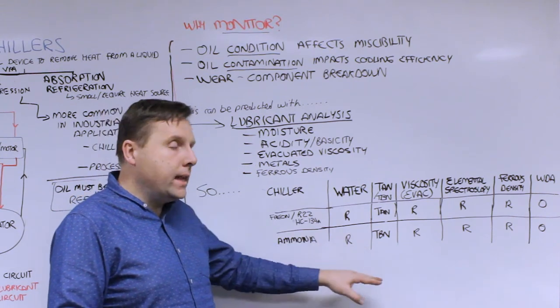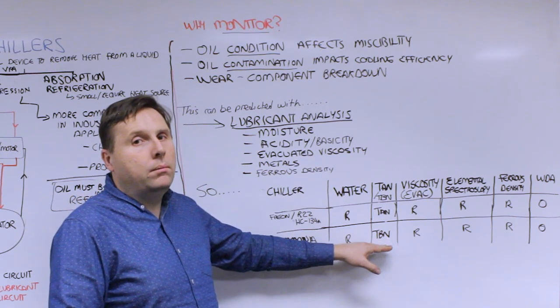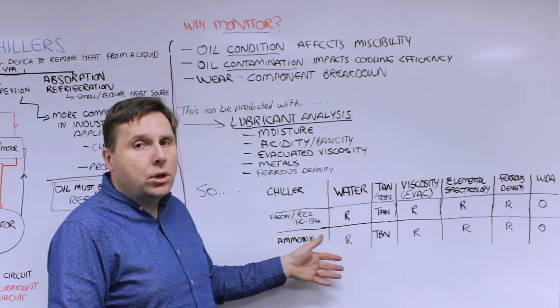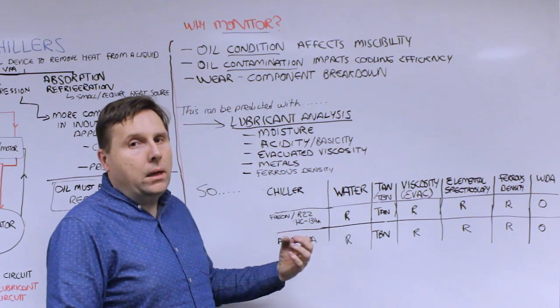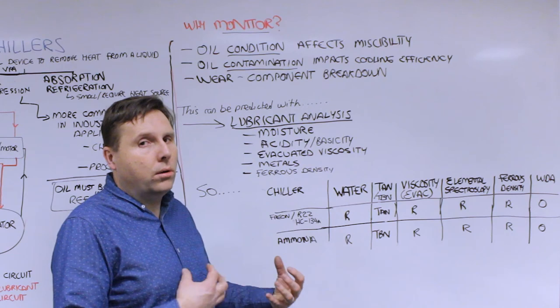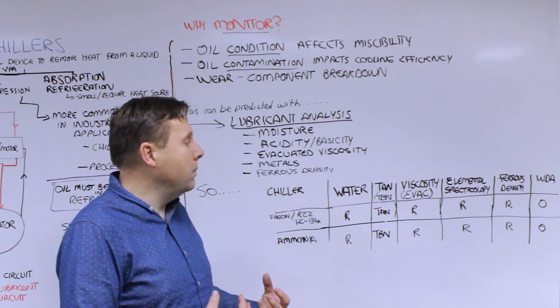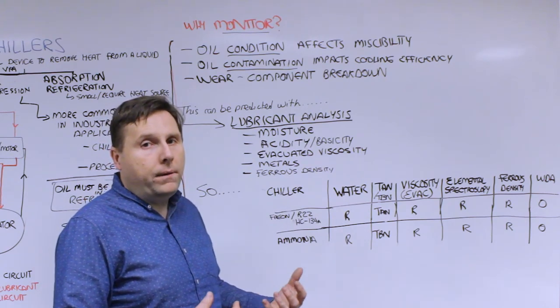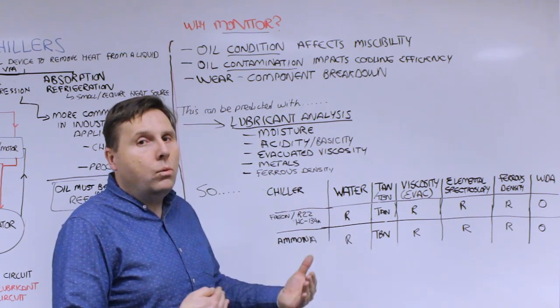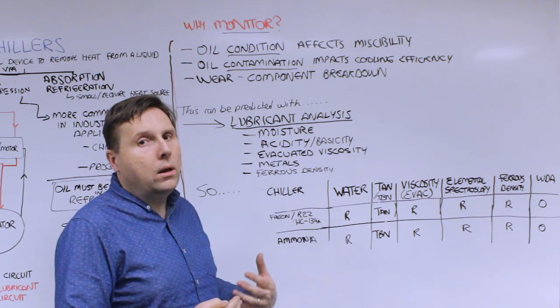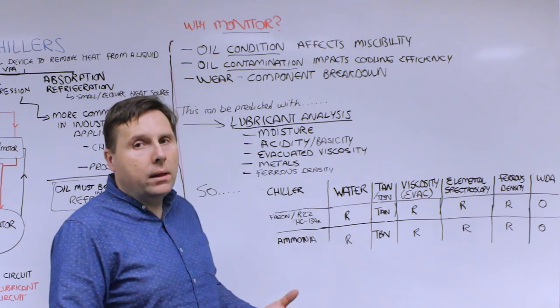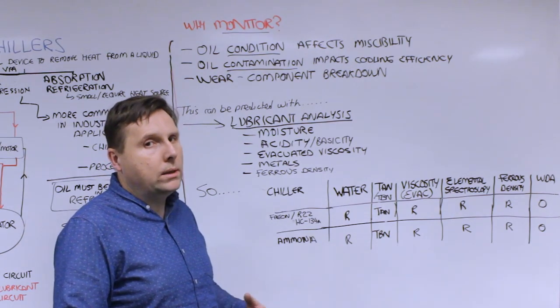High amounts of water present in a chiller can affect the evaporative capabilities, clog the check valve, and cause freeze issues. Acidity can affect the miscibility. If the viscosity is not within norms, it might indicate that the separator is not working properly and may need to be checked. Elemental spectroscopy tells you about wear metals as well as any additives that may be present, and ferrous density catches any large wear.